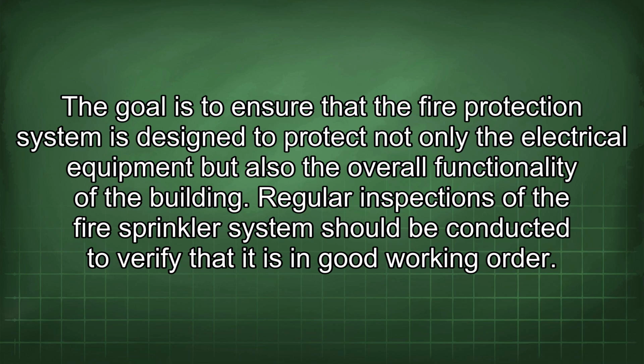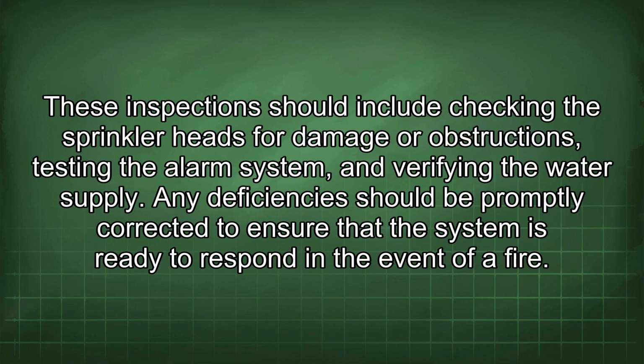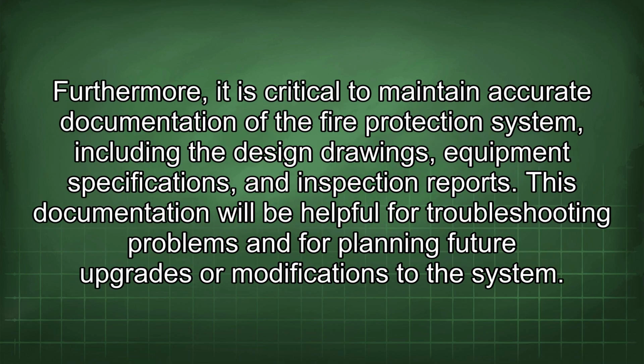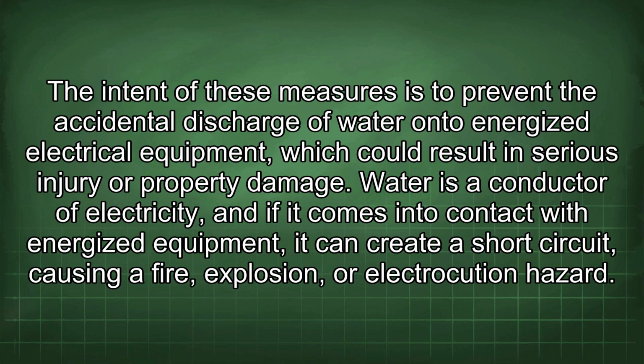Regular inspections of the fire sprinkler system should be conducted to verify that it is in good working order. These inspections should include checking the sprinkler heads for damage or obstructions, testing the alarm system, and verifying the water supply. Any deficiencies should be promptly corrected to ensure that the system is ready to respond in the event of a fire. Furthermore, it is critical to maintain accurate documentation of the fire protection system, including the design drawings, equipment specifications, and inspection reports. This documentation will be helpful for troubleshooting problems and for planning future upgrades or modifications to the system.